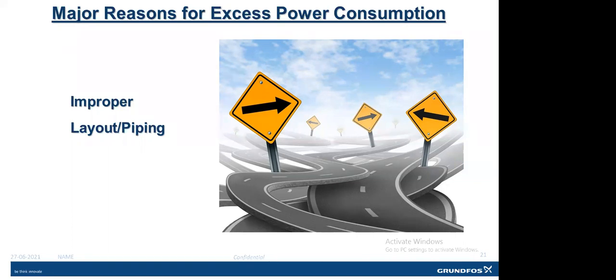Then we calculated the head with the existing pipeline and a proposed newly designed pipeline, and we calculated the power required for that flow with the existing under-designed pipeline and the properly designed pipeline. There was a 30% difference in the power consumption. For example, with the existing pipeline we needed around 100 kilowatts, and with the newly designed pipeline we needed only 65 to 70 kilowatts. So there was a direct energy saving just by changing the pipeline size. So always look at the pipeline sizes, whether the pipeline is designed as per our flow requirement and as per the best engineering practices.